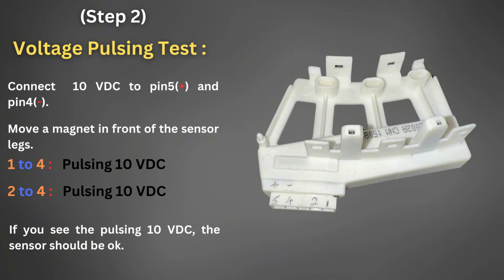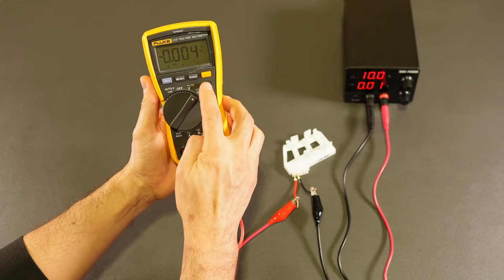The next step is the volt pulsing test. I'll use a new sensor to demonstrate. First, I'll connect pins 5 and 4 to 10 volts DC. Then I'll check the voltage pulsing between pin 1 and pin 4 and between pin 2 and pin 4. I'll move a magnet in front of the legs to observe the pulses.